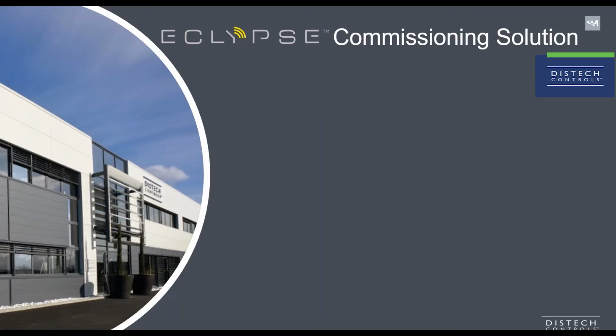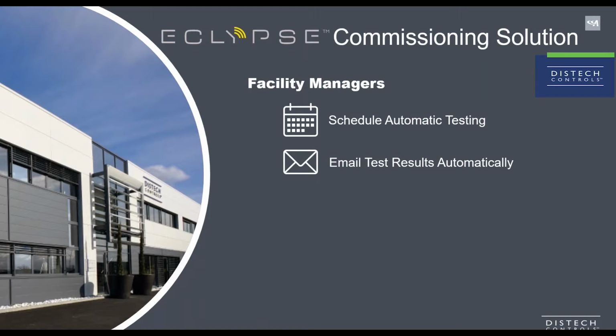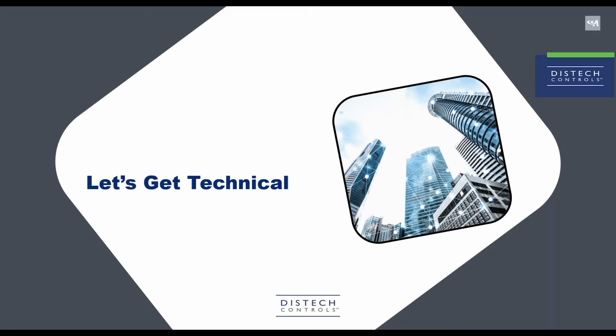How can this help my customers with their systems? The ECLYPSE Commissioning Solution is not only for system startups. You can enable the facility managers to schedule automatic testing at times that will not affect occupant comfort. These results will then be emailed to them upon the test completion. This will ensure that equipment malfunctions will not go unnoticed, which is critical for occupant comfort and well-being. Now it's time to get technical and show you what's under the hood.